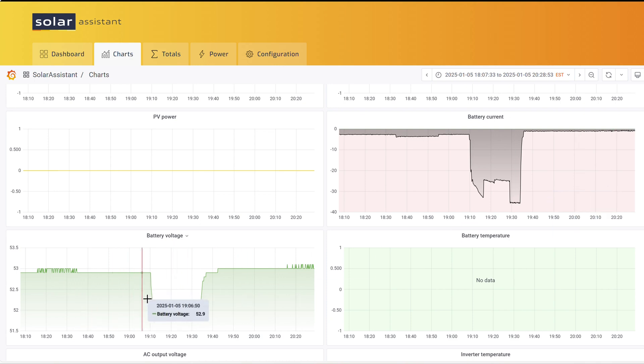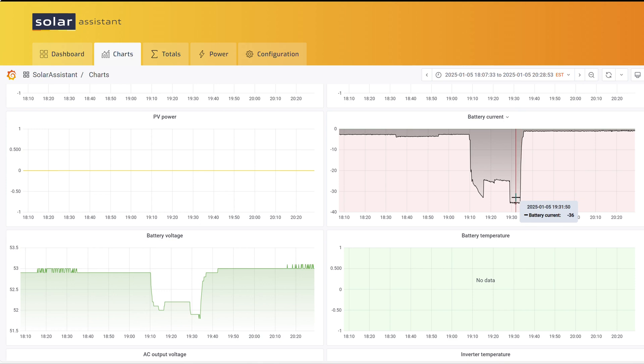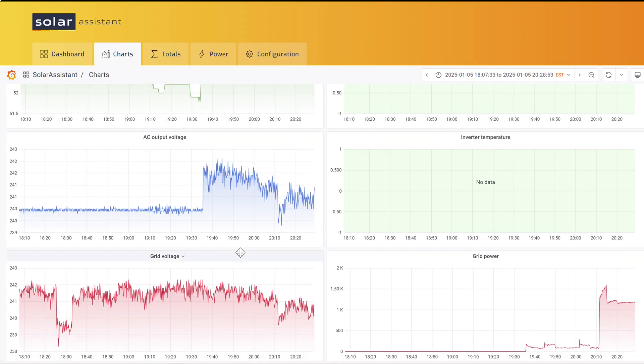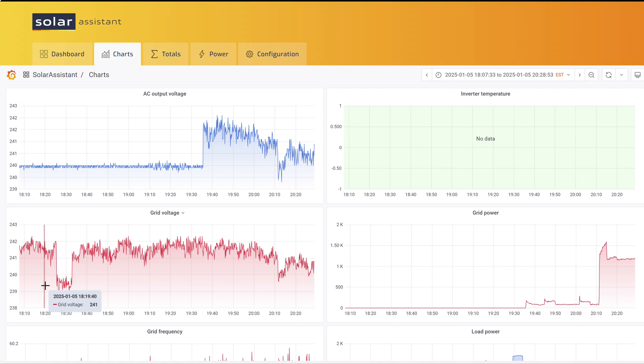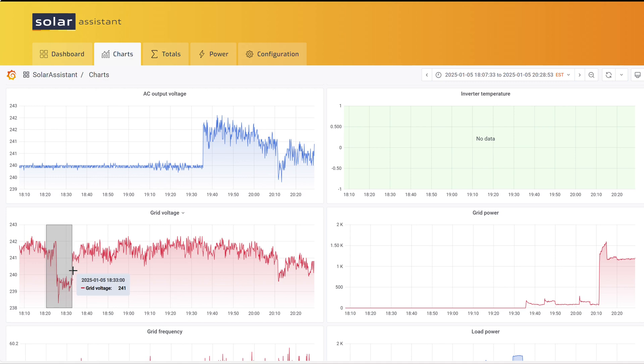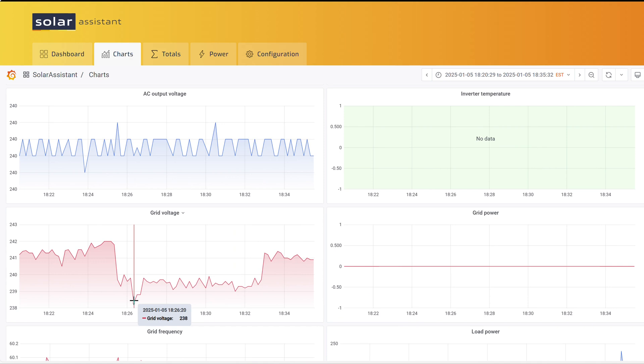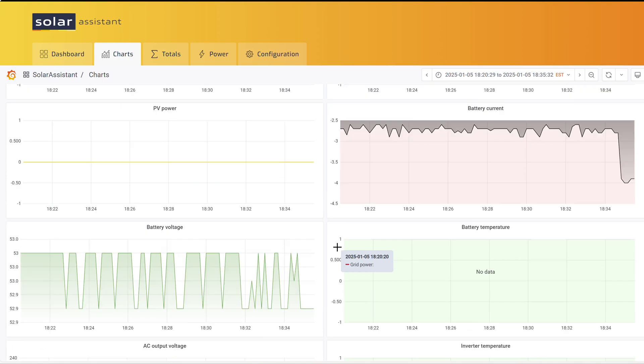But it allows you to kind of dig in and do some troubleshooting. Right. You might want to look at grid voltage, like right here and be like, gee, what happened right there? That seems like an anomaly in my grid. You can zoom in on that and get down and see, okay, well, my grid actually did dip to 238 volts for a second, which is fine here, but if it was a worst case, something different, maybe you had a little outage or there was some kind of quirk, there's an event you can go back and you can look at that data here. So that's kind of what solar assistant allows you to do.